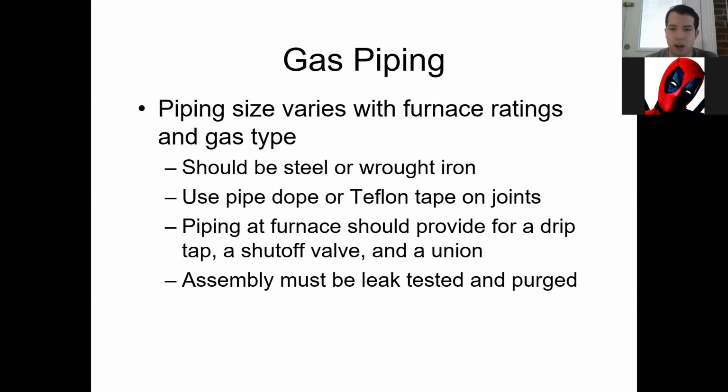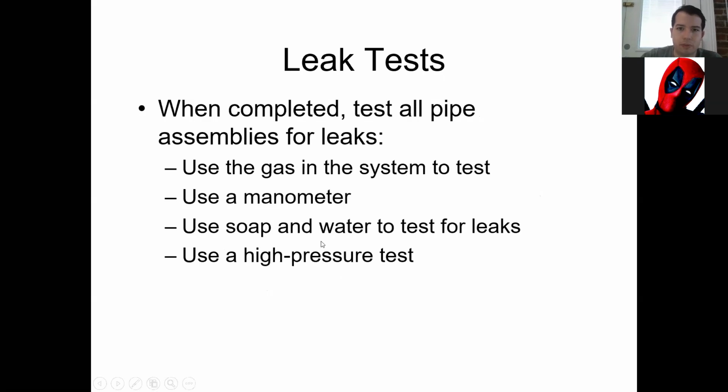Okay. But yeah, you're basically going to leak test all of your connections when you do an install, to make sure it's working properly. The last thing you want is a gas line just leaking like crazy. So leak test, like I said, there are a couple of different styles. The soap and water test is an easy one, but a manometer can also be used on what's called a lockout test.